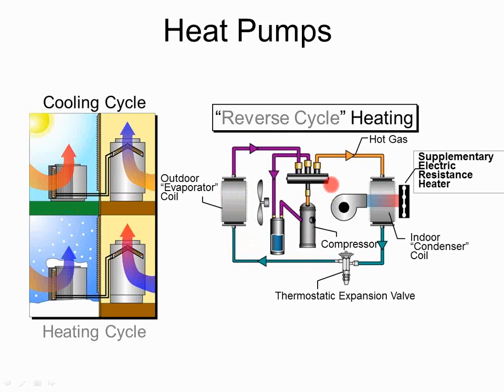The main component difference is I have a reversing valve, which is right there in the center with the 3 pipes on top, 1 on the bottom. The reversing valve basically just changes where I decide to send the refrigerant, right? So instead of taking refrigerant from my outdoor unit and sending it to my TXV, I take refrigerant from my outdoor unit and send it to my compressor, right? And then over to my indoor coil, then to my TXV, right? So instead of going TXV, evaporator, compressor, condenser, it goes the opposite way. It goes from the outdoor unit, which is now the evaporator, into the compressor, and then out of the compressor to the indoor unit, and then to the TXV, and then back around the loop. The whole cycle just goes in reverse from a traditional air conditioner.